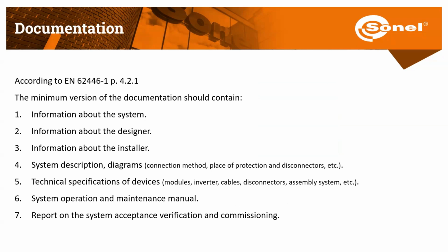During the visual inspection, we should also check the system documentation. The minimum required documentation is described in the standard. This documentation should contain information about the system, the designer, the installer, system description, diagrams, technical specification of devices, system operation and maintenance manual, and of course a report on the system acceptance, verification, and commissioning. So this is the minimum documentation that every PV system should have.